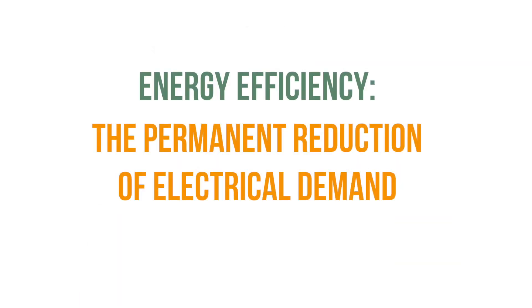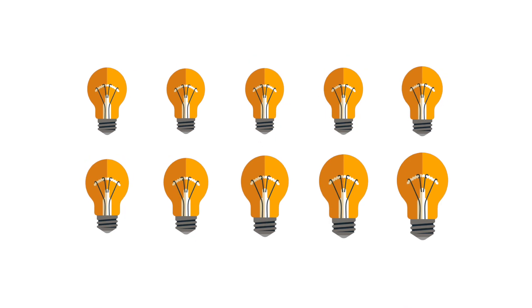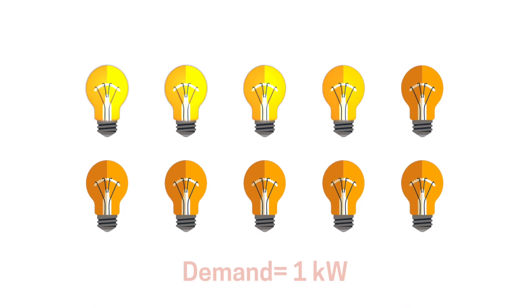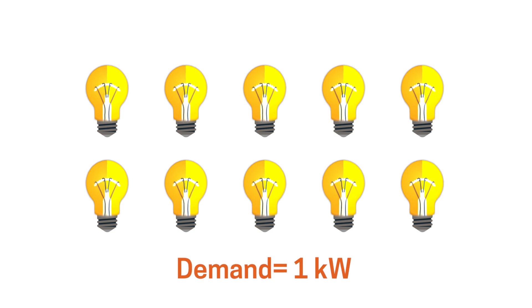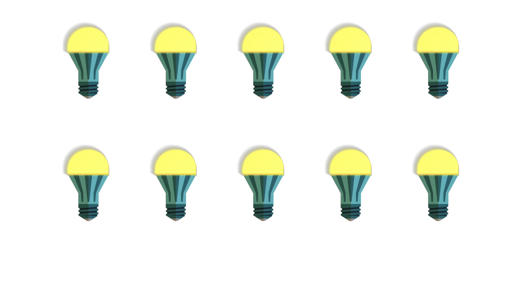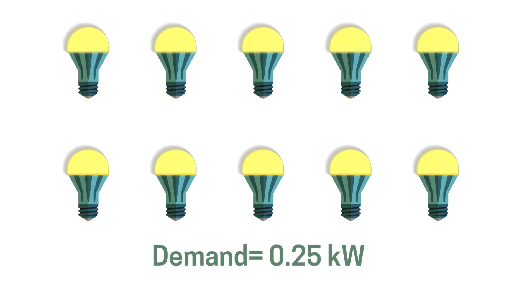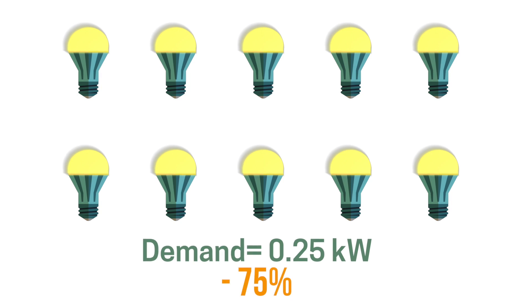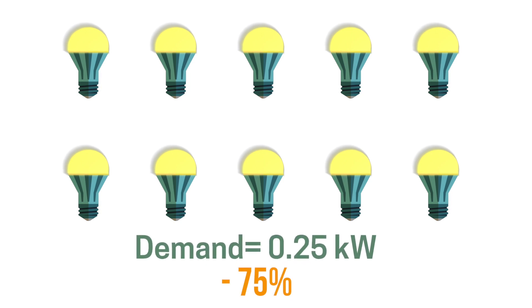Now let's return to our definition of energy efficiency—the permanent reduction of electrical demand. With energy efficiency, you reduce your electrical demand permanently, thereby reducing the amount of electricity the utility has to have constantly ready to meet your needs. Now imagine we replaced our bank of 10 100-watt light bulbs, which has a demand of 1 kilowatt, with 10 25-watt LED light bulbs, which have a total demand of 0.25 kilowatts. We've reduced our demand by 75 percent, saving us money on demand charges assessed by the utility, who has to be ready to meet our demand.